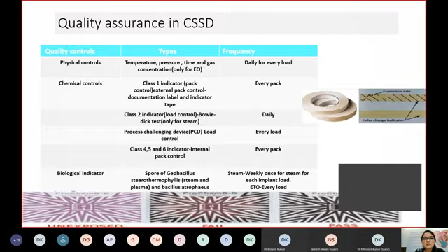And the last one is the biological indicator. We use different types of bacillus: Geobacillus stearothermophilus for steam, and Bacillus atrophaeus for ETO, and these are very good indicators. But the problem is that they take a pretty long time to show the results. The good news is that rapid technology has now come in, which can give you the results for the biological indicators in 1 hour, 3 hours, and 4 hour intervals.